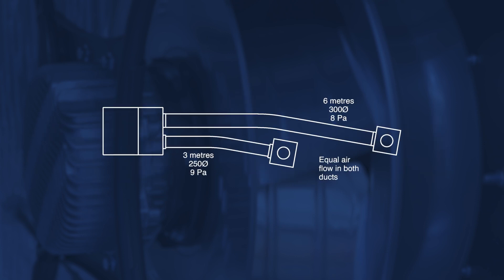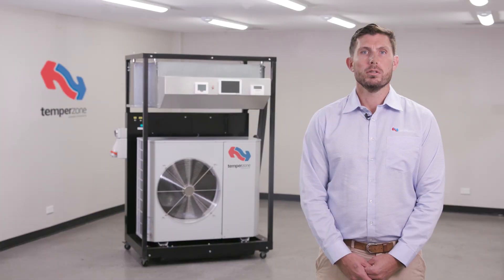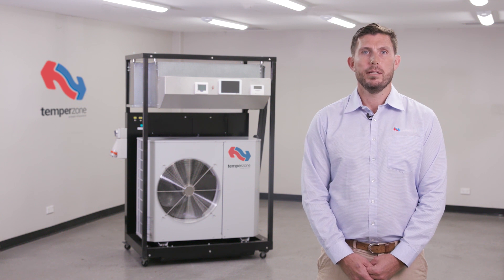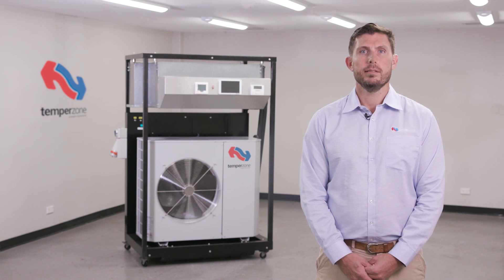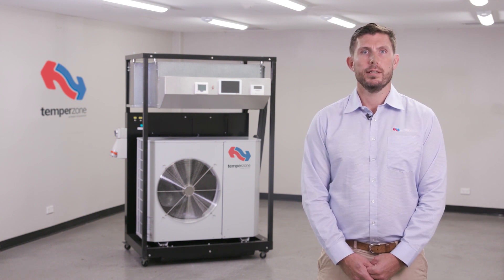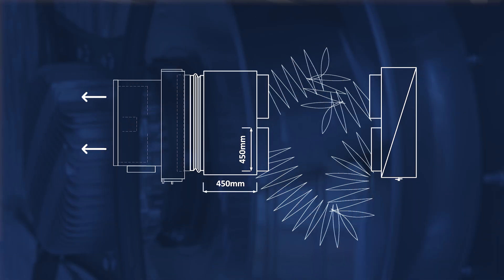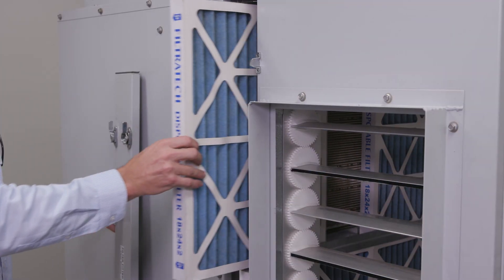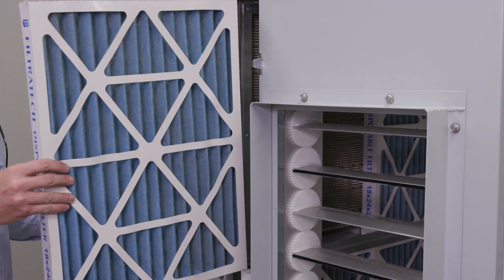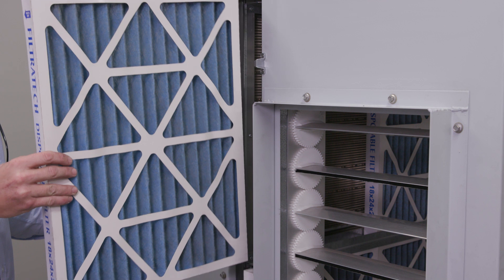Oversize the flexible duct for long runs. It is not recommended to install flexible duct longer than 6 meters. Should longer than 6 meters be required, it is suggested to incorporate some rigid straight circular duct. Do not coil up surplus flexible duct for short runs — cut to suit.